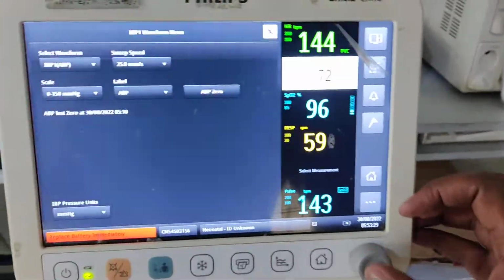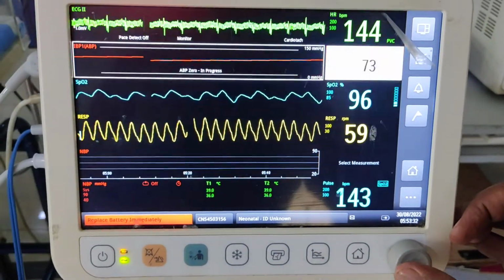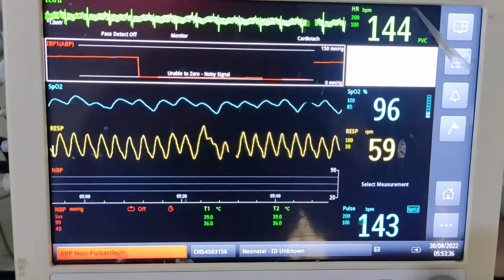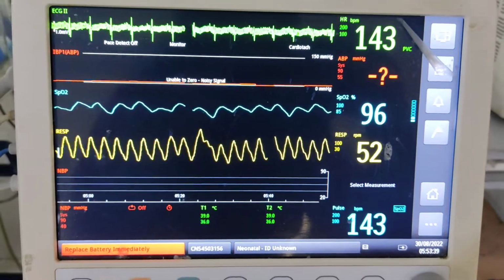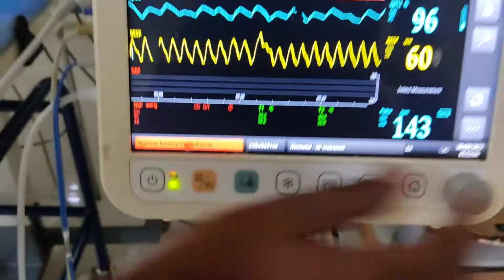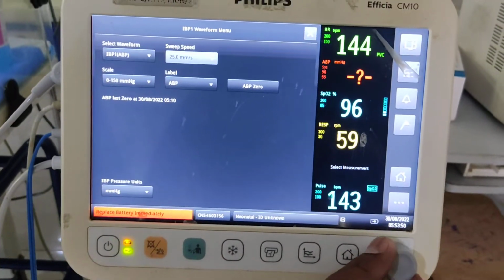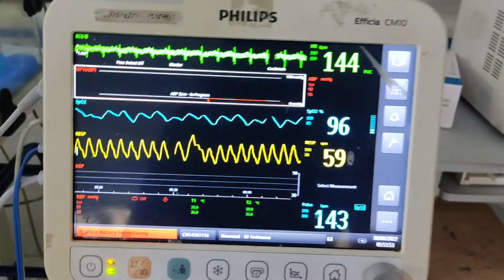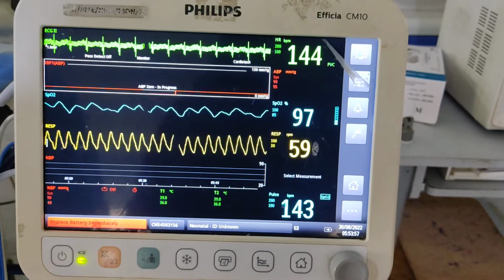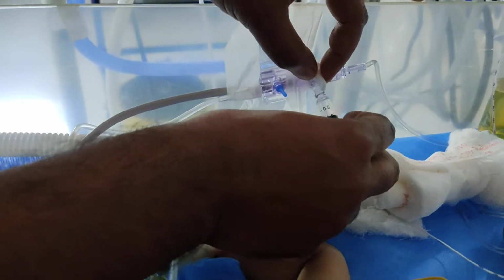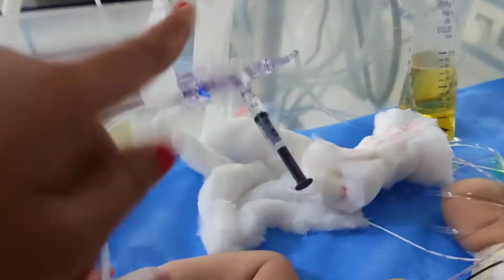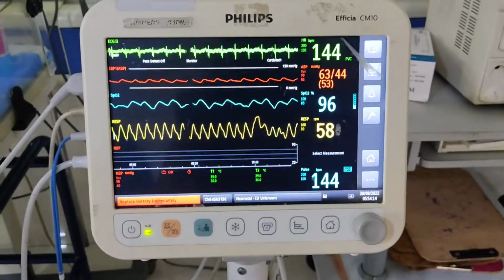Okay, the one which goes to the arterial end, and now we have to make this 0. Okay, bring this to NIBP and press this ABP 0. Then you can see ABP 0 in progress. Unable to 0, so we have to go again one more time. One more time. Yeah, so you can see ABP 0 is complete. Now open the arterial end towards the syringe. So the syringe is blocked, arterial end is open now. So you can see the waveform will come, and the arterial BP monitoring is going on.